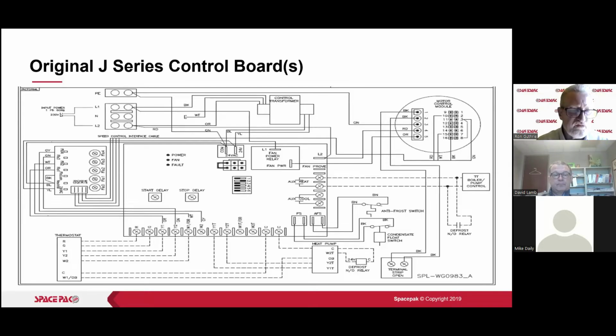That's where we adjusted the speed on this. So we did a lot of things manually on the J series units that we now do on board, literally, with the J plus series units. And one of those things was that we set up that EVO board for heating 1, heating 2, cooling 1, cooling 2, and fan only through little rheostats, and you'll see those in the pictures coming up.